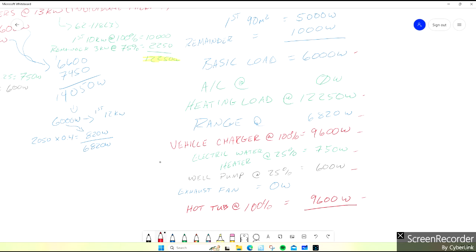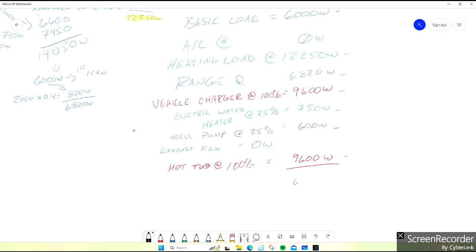So let me add these up. We got 6,000, 12,250, 6820, 9600. Make sure I don't fat finger my calculator. 750, 600, and 9600. That gives us a total wattage of 45,620 watts. Let me move that down, and a different color, just to separate everything. That's the demand on this home.